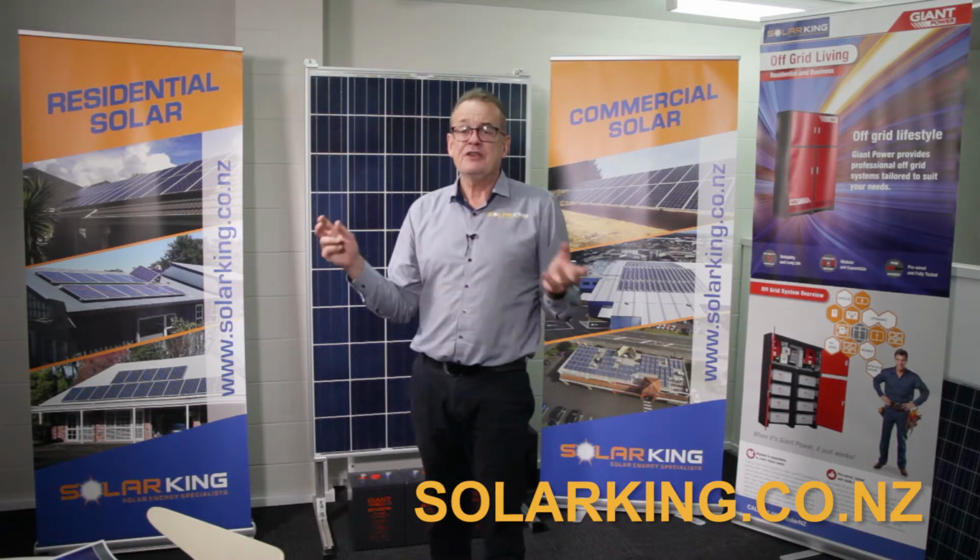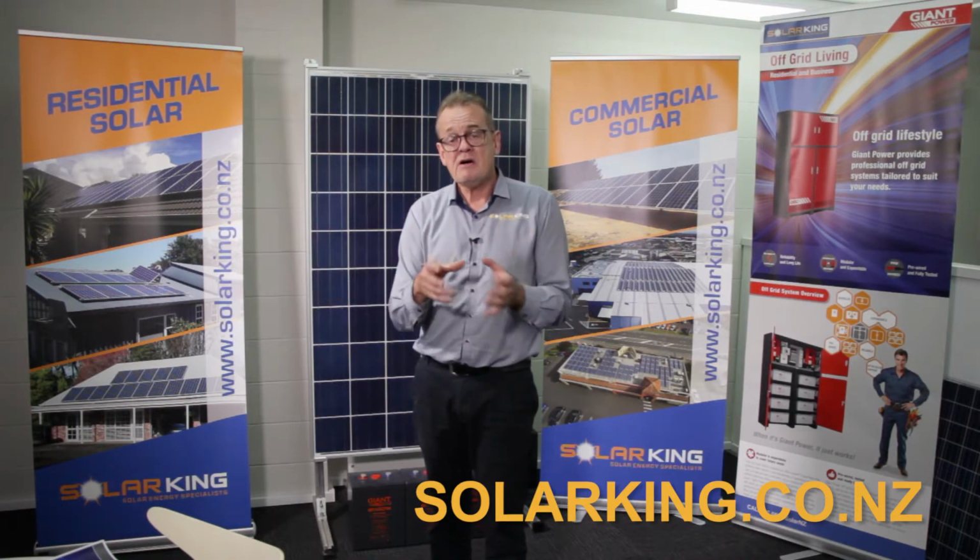Another client has a 3D printing operation where they're printing high value 3D products. Now these print runs can take between 12 and 24 hours, and if he has a power outage in that time and it interrupts the print run, it's wasted and they've got to all be thrown away. So we're putting in a battery bank alongside his existing solar that will give him enough power from the battery bank to run his machines for 2 hours, because he has a backup generator, but should the interruption happen at midnight, he needs to get the phone call, get down there, turn the generator on and make sure everything keeps running. So our concept of a solar powered emergency power supply, or UPS, has merit in many situations.